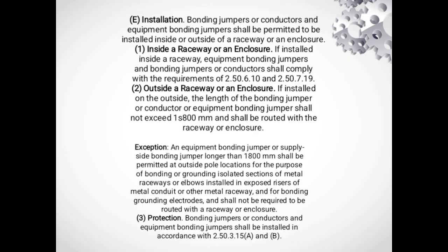Exception: an equipment bonding jumper or supply side bonding jumper longer than 1800 mm shall be permitted at outside pole locations for the purpose of bonding or grounding isolated sections of metal raceway or elbows installed in exposed risers of metal conduit or other metal raceway, and for bonding grounding electrodes, and shall not be required to be routed with a raceway or enclosure. Number 3, protection: bonding jumpers or conductors and equipment bonding jumpers shall be installed in accordance with 2.50.3.15 A and B. Size: equipment bonding jumper on load side of an overcurrent device, and insulation.